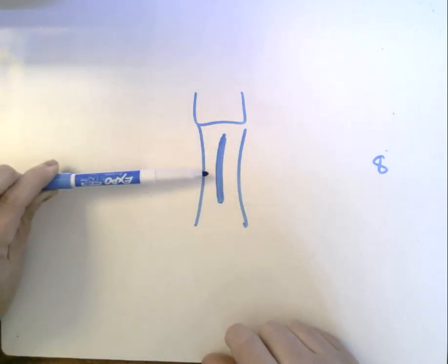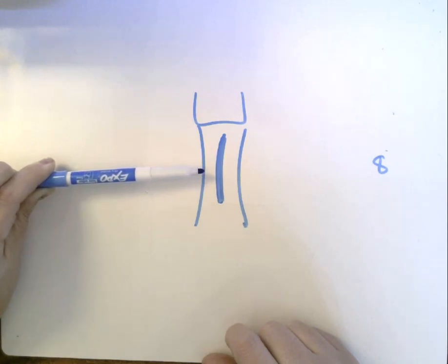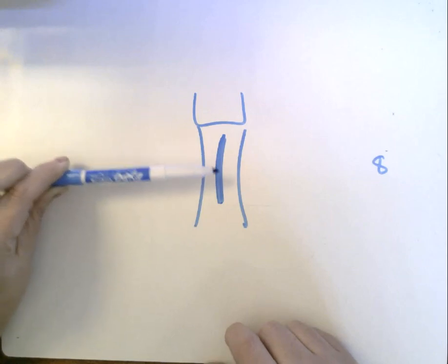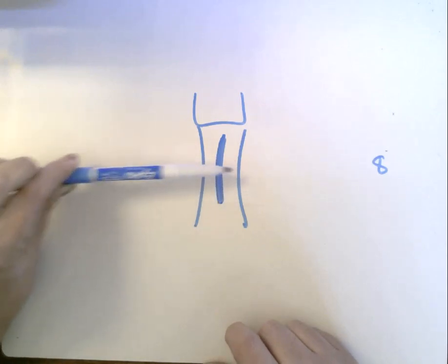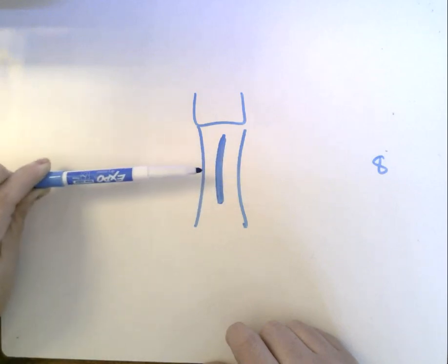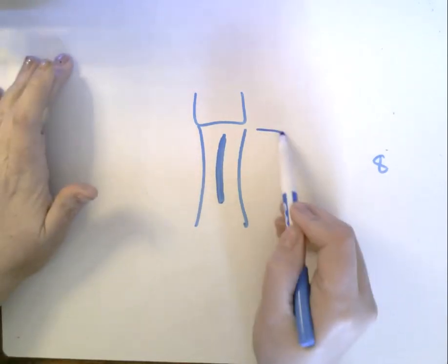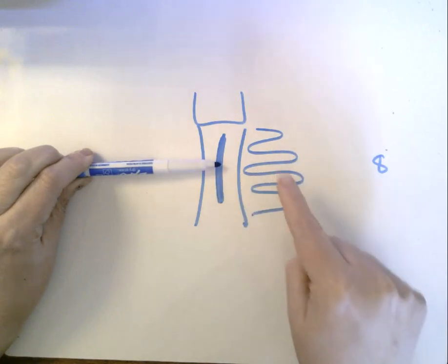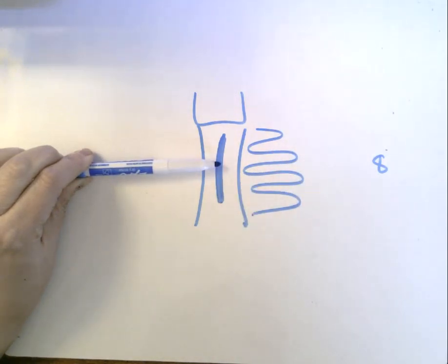So if I stick it in right in the edge here, the hydrophone would recognize what the intensity is on the edge. And then if I move it towards the center of the beam, it would be able to measure those center peaks, those spatial peaks. And then I can move it around and I can get very exact intensity measurements while I move this around in space. Now, the other thing that we know is that we're going to have different intensities coming down, right? So if I hold it here in the spatial peak, at some point, I will get that temporal peak during that time as well. And so we would be able to measure that.